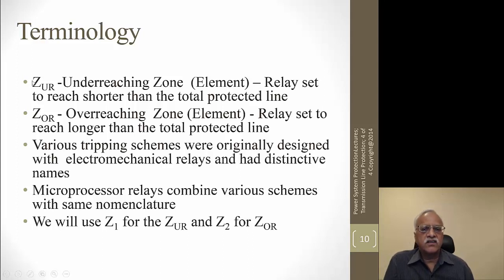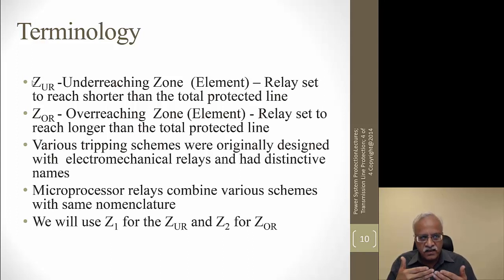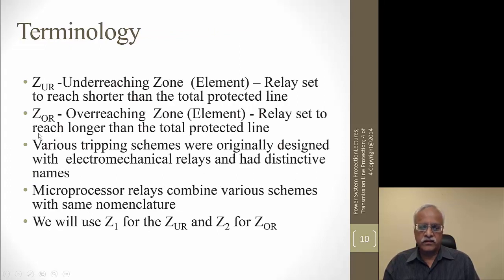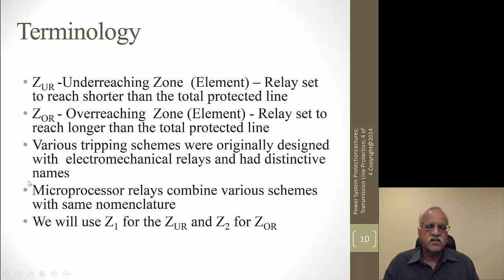Before describing the schemes, let me introduce the concept of underreaching and overreaching relays. An underreaching relay is one not set to 100% of the line section — only to about 85%. That is called underreaching, and in our case, it is zone 1. An overreaching element is set greater than the line impedance and can detect faults beyond the line section — in our case, zone 2. Microprocessor relays use the same nomenclature. There are different schemes based on electromechanical relays that have now been adopted by microprocessor-based relays, and you can combine any combination of scheme types.